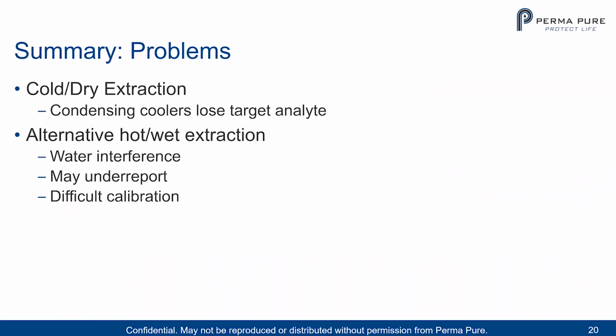So let's go through a final summary. With cold and dry extraction, condensing coolers lose the target analyte, and that's really why our products have become so important in this industry, because when you're looking at low-level SO2, it's really the Nafion dryer that's going to preserve that SO2 in the sample and get an accurate result. And I think that's very important to note. A lot of people are using the alternative hot-wet extraction, but we're seeing a water interference there that is changing the measurements. You're also not getting the best results with FTIR, and you might be underreporting the level of SO2 in those measurements. And also calibration is difficult to get to work properly.